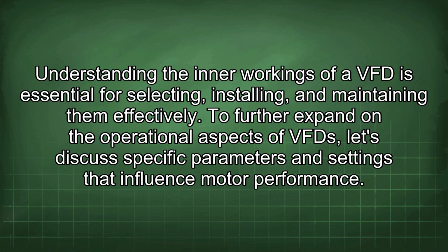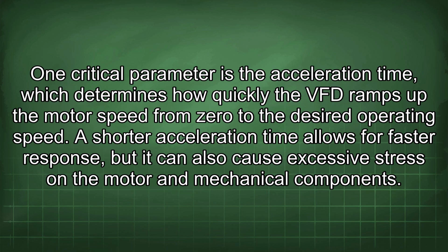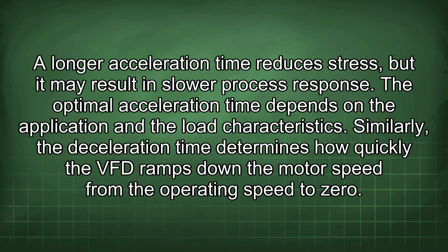To further expand on the operational aspects of VFD, let's discuss specific parameters and settings that influence motor performance. One critical parameter is the acceleration time, which determines how quickly the VFD ramps up the motor speed from 0 to the desired operating speed. A shorter acceleration time allows for faster response, but it can also cause excessive stress on the motor and mechanical components. A longer acceleration time reduces stress, but it may result in slower process response. The optimal acceleration time depends on the application and the load characteristics.